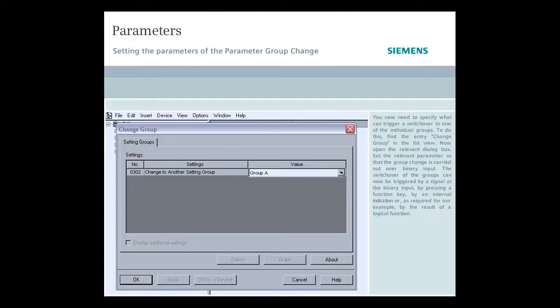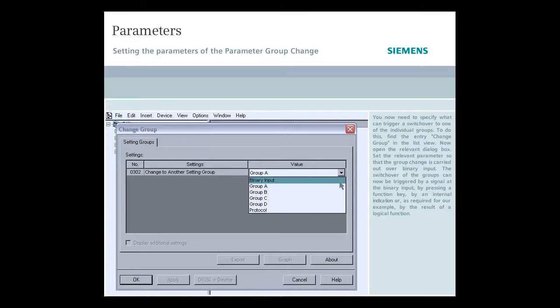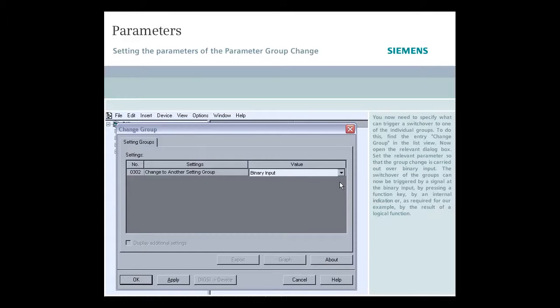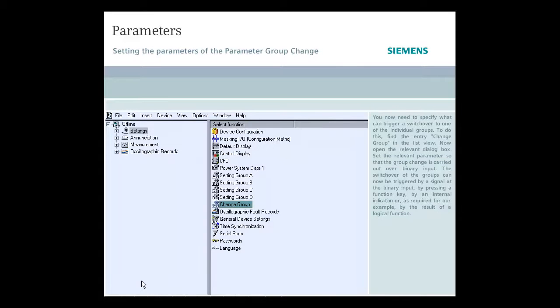Set the relevant parameter so that the group change is carried out over binary input. The switch over of the groups can now be triggered by a signal at the binary input, by pressing a function key, by an internal indication, or as required for our example, by the result of a logical function.